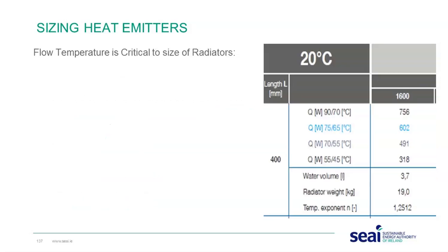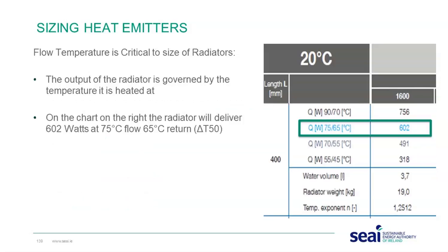Why do we need this? As I've mentioned before, the flow temperature is critical to the size of a radiator. The output of a radiator is governed by the temperature it's heated at, so the rate of exchange depends on the difference in temperature. The chart on the right is how one manufacturer demonstrates their outputs.